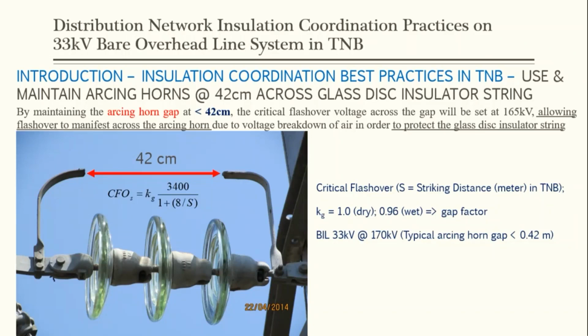So we have to look back at the definition, acceptable failure rate. So we allow the air to break down. So we have the air insulation and the solid insulation of the glass disc insulator. So what happens here is that we allow the insulation breakdown of air, right, to protect the glass disc insulator. Instead of having a permanent interruption of our overhead line, we allow transient interruption for a very short period of time with fast restoration. It will be cumbersome, or it will be detrimental, if we allow the glass insulator to be damaged due to the high impulse, because that will cause permanent interruption to our system, causing a longer duration of power outage to our customer. So this is how coordination works.